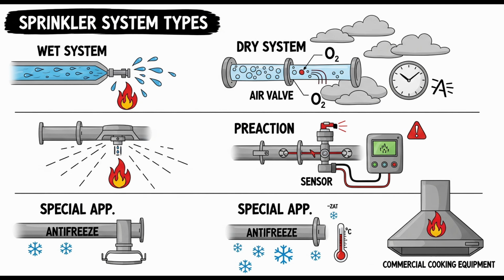Okay, let's move to antifreeze systems. These are for protecting smaller, limited areas subject to freezing temperatures, typically connected back to a main water supply, maybe a wet pipe system. Right. Instead of using complex dry or pre-action valves for just a small cold room or entryway, you can sometimes use an antifreeze system. The pipes in these small localized systems are filled with an antifreeze solution instead of plain water to prevent freezing. Seems straightforward. What are the key requirements?